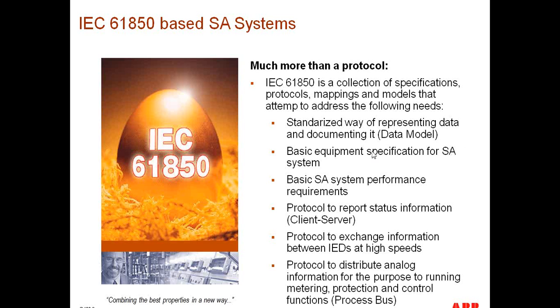We also define basic equipment specification for the substation automation system. What this means is there are certain specifications for the hardware that makes up the substation automation system in regards to dielectric, in regards to SWC, surge withstand capability, and so on. So there are some quality standards associated with the equipment that it needs to meet in order to be part of an IEC 61850 system. The standard also defines performance requirements in regards to the speed and reliability of communication messages. This is something that's very important. So there are different classes of performance defined, and depending on the type of message, the message should be delivered within that period of time.